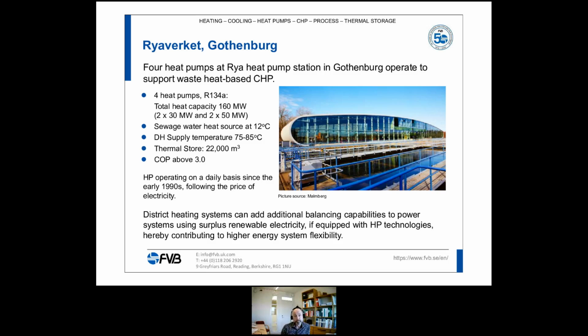And during this time period, we have only seen a few component failures, telling us that it's close to the limit with respect to mechanical wear, but you can really run a plant this way. It's quite a big thermal storage, and it's huge heat pumps as well. But the size of the storage actually makes it possible to run heat pumps full load at 6 hours only on the storage.